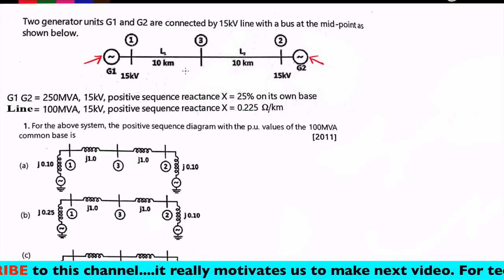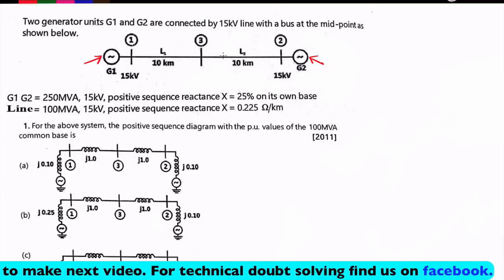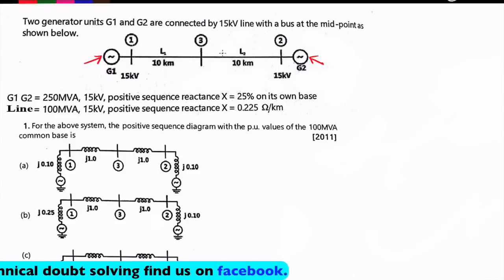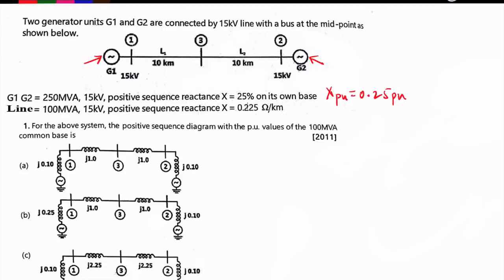There is no transformer connected, so throughout the line the voltage is 15 kV only — considering this is a lossless line. The length of line L1 is 10 km between bus 1 and bus 3, and L2 is 10 km between bus 3 and bus 2. The rating of generators G1 and G2 is 250 MVA at 15 kV, and the positive sequence reactance is 25%, so X per unit = 0.25 pu on 250 MVA base.